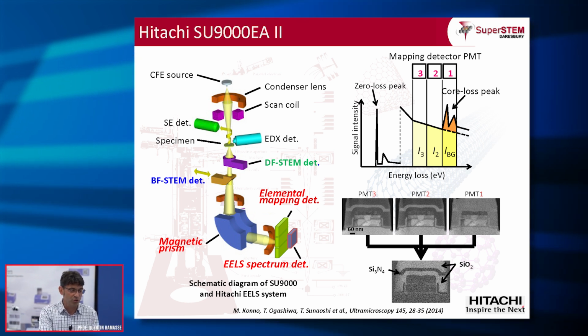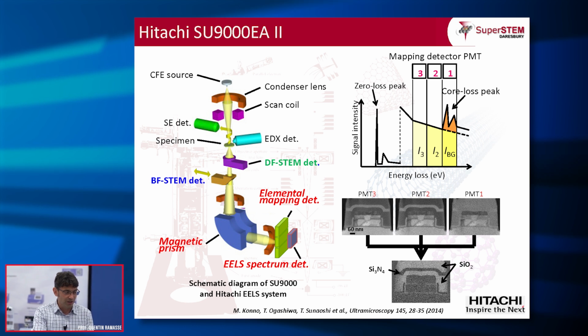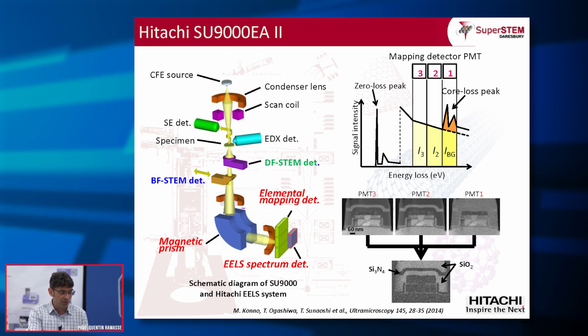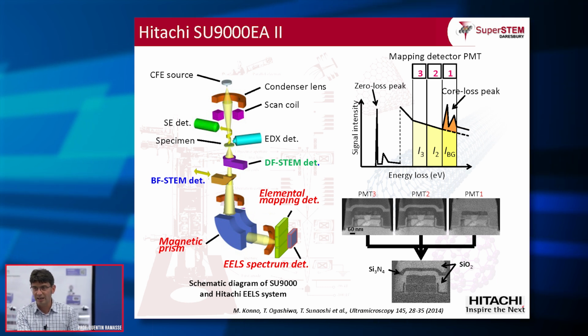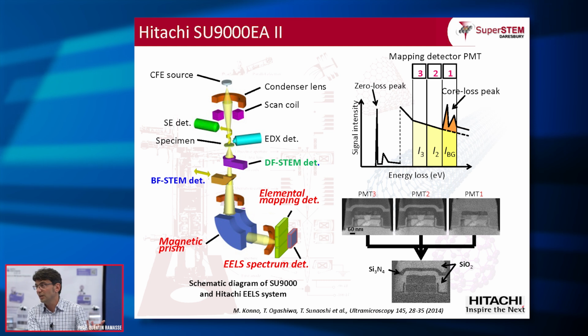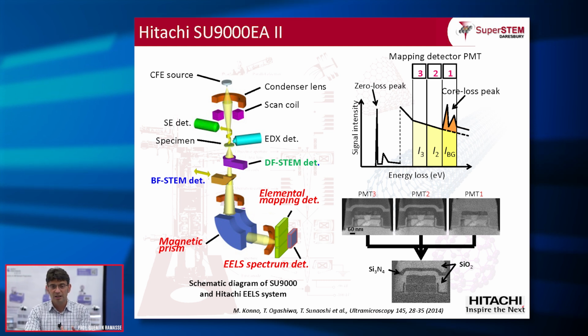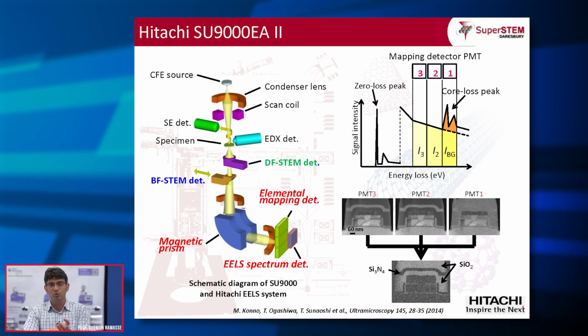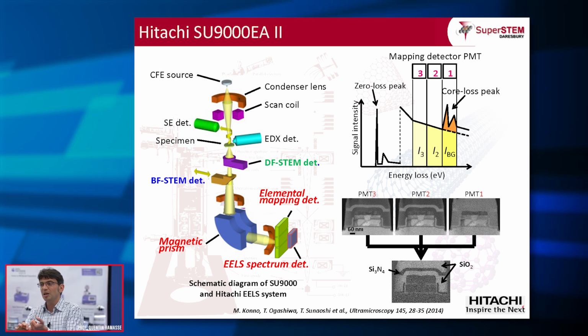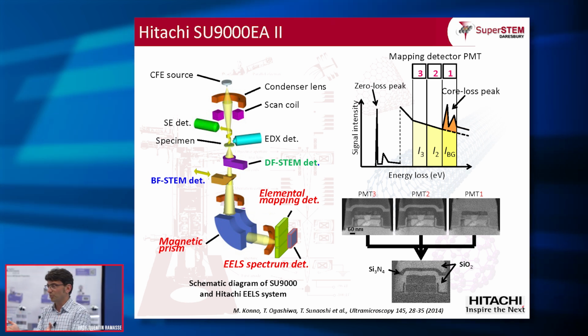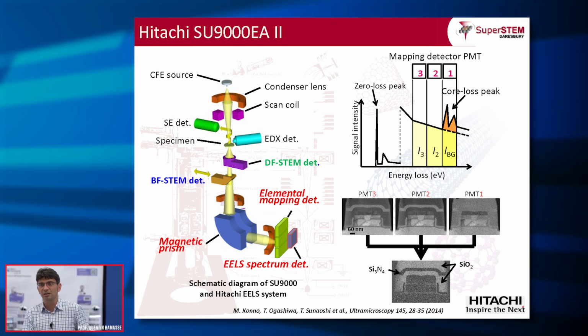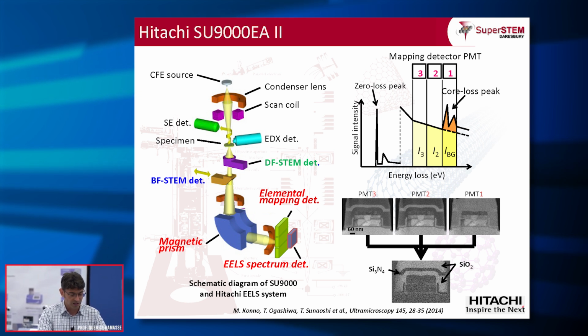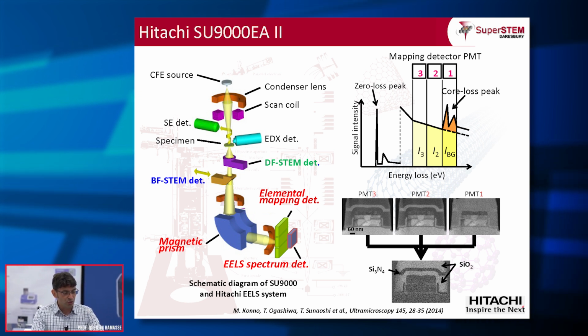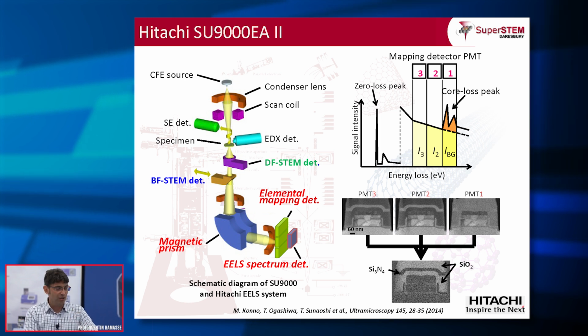It's very simple. It just has a source, some sort of lens focusing the probe on the sample, and then a bunch of detectors. What's really important is it has this EELS spectrometer at the back end, which allows us to do EELS, but also EDS, so we can do EELS and EDS simultaneously. And we're very strongly pushing our friends and colleagues in R&D to also add things like 4D STEM, maybe some sort of post-specimen optics, without making it too complicated, but certainly making it even more flexible. It has 2 detectors in EELS, and again, Muto-san can answer if you have any questions.